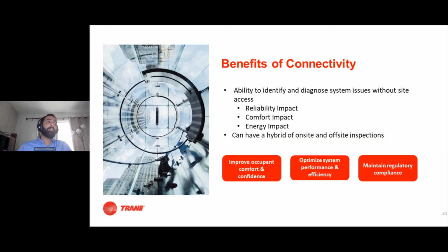Furthermore, the benefits of connectivity, there's also the reliability impact, the comfort impact, and the energy impact. So maybe you have a ducted style indoor unit where the filter's not been cleaned. That's now going to impact your comfort, your reliability, and your energy. Now we can look at that remotely, point that out as an issue, and then suggest some fixes for that. While I did mention 3 quarterly remote checks and 1 on-site check, we also have a multiple of hybrid options available that are very non-intrusive.